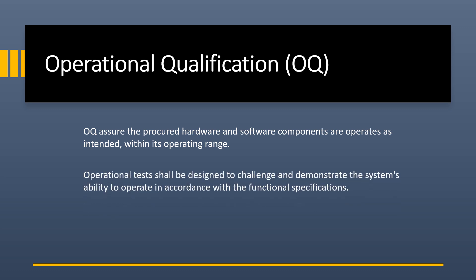Operational tests shall be designed to challenge and demonstrate the system's ability to operate in accordance with the functional specification. Whatever privileges and functions are available with the software, we need to challenge them. Also, tests related to 21 CFR Part 11 or EU Annex 11 need to be performed.